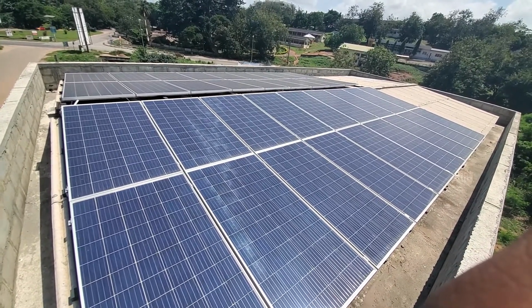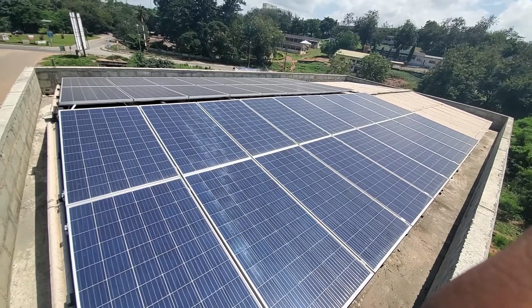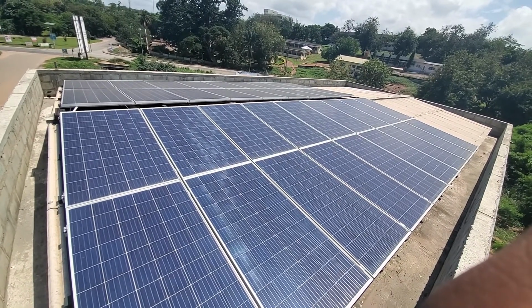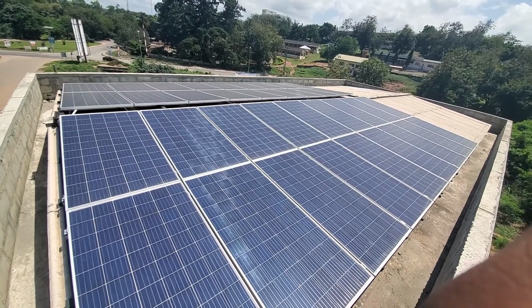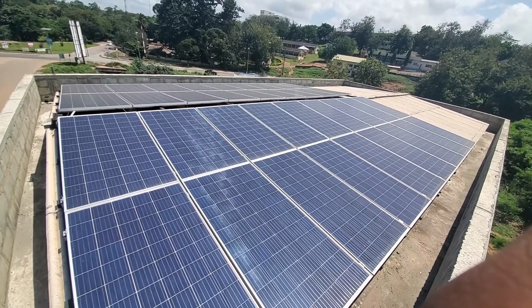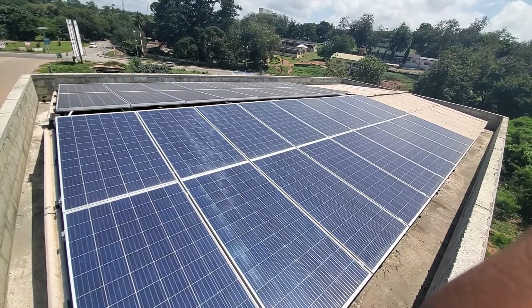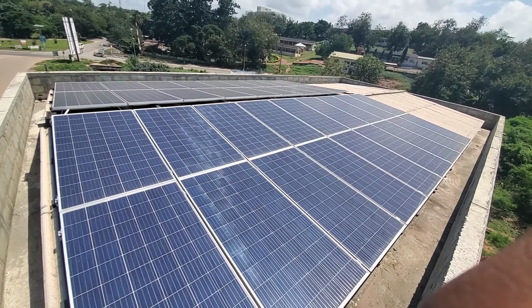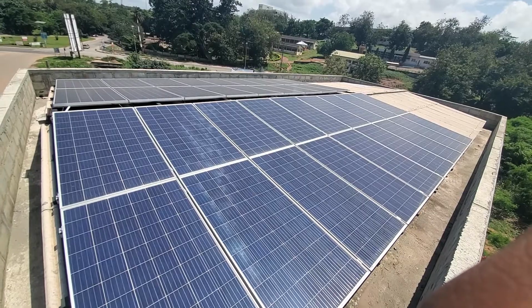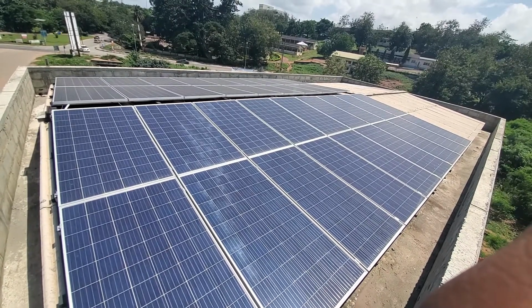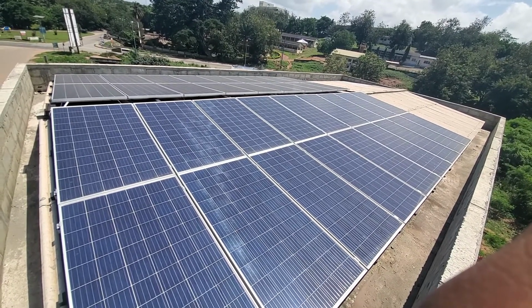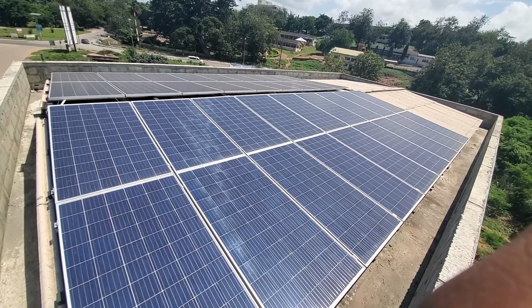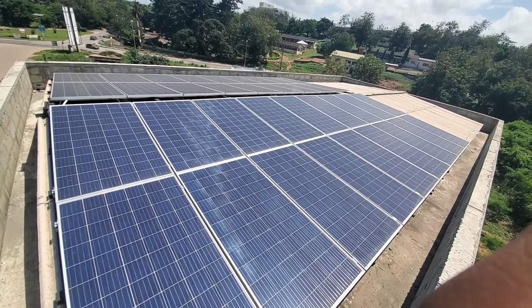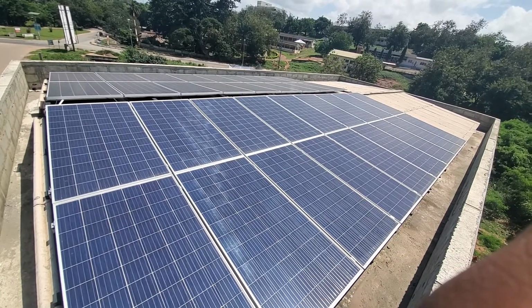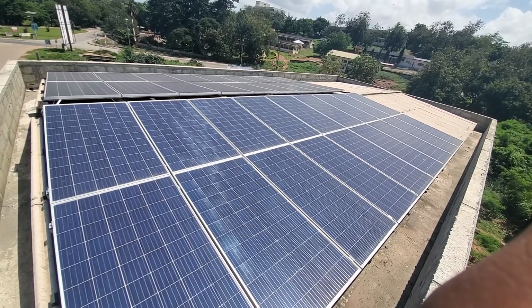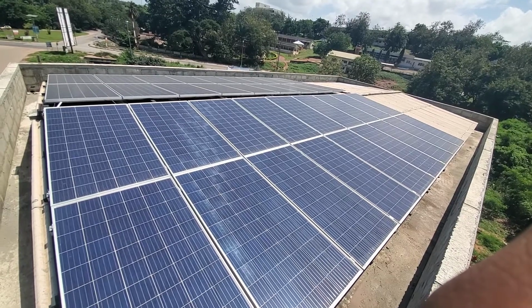As you can see, we have 9 of these panels in series, and then we have 4 in parallel. Each of the panels, the brand is JA Solar. The maximum power is 325 watts. The VOC, we call the open circuit voltage, is 41.04 volts. And the maximum power current is 9.72 amps.